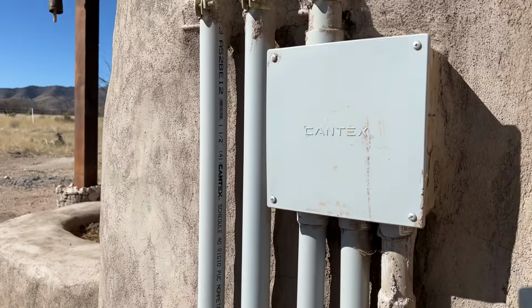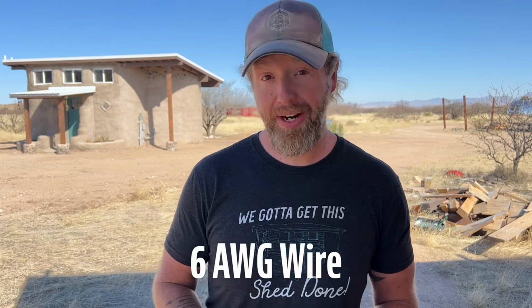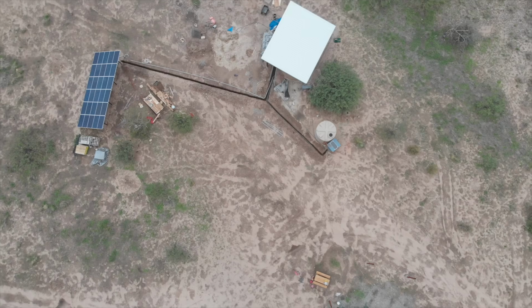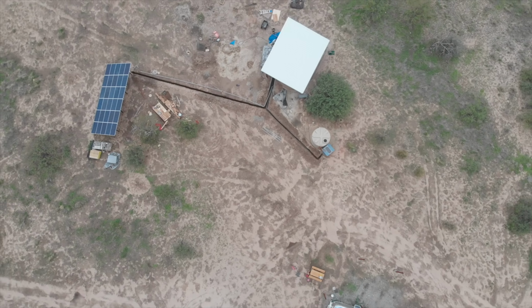Because of the length of the run and the amperage, we used 6 gauge wire which will actually allow us to increase our panels if we ever need to. But this ran through 1.5-inch conduit through multiple twists and turns, and we dug it all by hand, and it was ridiculous, but we got it done.